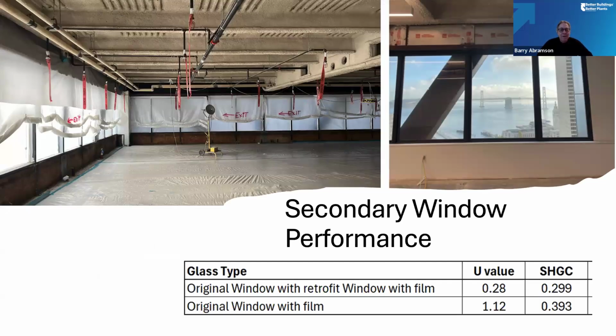So let's look at what happened. Here you can see some pictures in action. The one on the left is in progress. On the right is a picture of an office where secondary windows were installed. The perimeter induction units are gone. And if you look at the comparison of thermal performance, the retrofit brought the U value down from a little over 1.1 BTUs per square foot down to 0.28. And solar heat gain coefficient also was reduced pretty substantially as well. So a very, very dramatic impact on the loads.